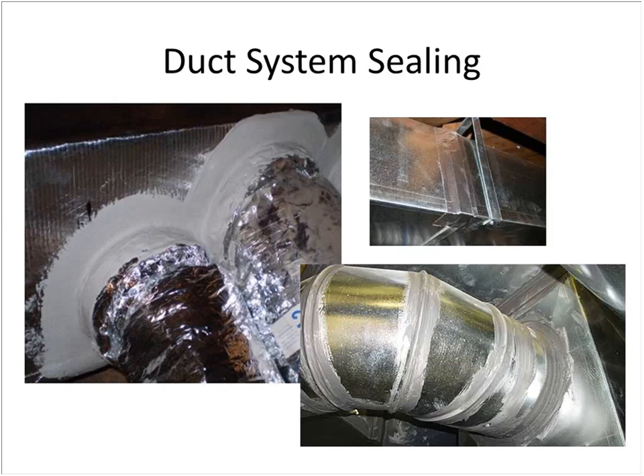This is an example of some air sealing detail. The one on the left is an insulated duct in an attic space, and they've got flex duct to it, and you can see that they've made judicious use of mastic to seal those connections to prevent any leakage. And it's much better than the tape that they use.